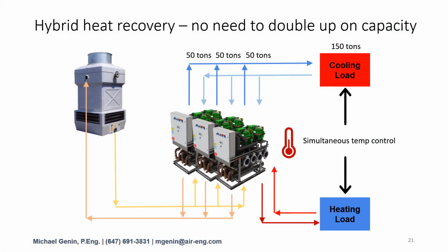Another implementation of hybrid heat recovery, in this case, the load is still 150 tons like we showed in the previous example with the main chiller, but we've installed a secondary condenser on the third chiller module furthest to the right. In this case, the heat recovery load is small and served only by this third chiller. However, it could be set up that all three chillers have the hybrid heat recovery feature. In this case, the first two chillers on the left are rejecting heat to the cooling tower only, and the third chiller has the ability to reject heat to either the cooling tower or the heating load.